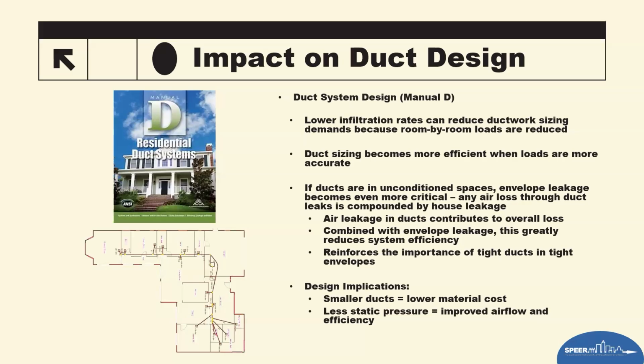Having ducts tested and verified that they meet the requirement of the code is mandatory, but it's also one of those things where it really should happen on every single house. Design implications: smaller ducts equal lower material costs, of course, same as equipment, and then, of course, less static pressure, improved airflow and efficiency as well.